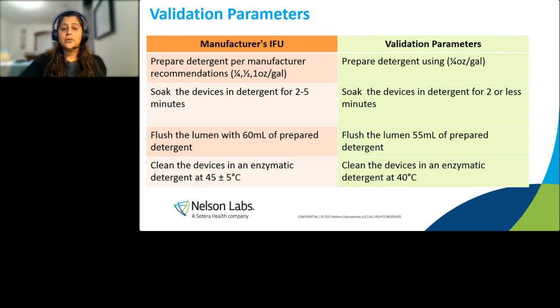Now, for the validation parameters, this is your manufacturer's IFU that you would see at your end. The validation parameters are what we would do on our end, where we would challenge it to the lowest dosage. We would soak it to the lowest time. We would flush with less detergent, and we would use the temperature that is specified to the lowest. This is what we would challenge for the processing, just to make sure that if time is not permitted and you have to do it at 2 minutes instead of 5 minutes, the 2 minutes is validated. Because if less is validated, then more is fine. So our validation procedures always go to the worst case process, where we would go on the lower end of everything.